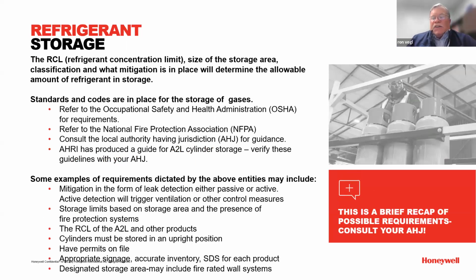Refrigerant storage — I'm not an expert on this, but if you're going to have a lot of refrigerant storage, even A1s, there are restrictions on refrigerant storage now. The best guideline we can give you is, and I know everyone hates to bring an inspector into your business, but you need to be safe. Get OSHA, get your local inspector. AHRI is putting some guidelines out. It's pretty substantial on what you can store, but you need to be clear on whether it has to be in a caged area or open air, whether your building is sprinklered or ventilated. Then there are differences on how much refrigerant you can keep in stock.